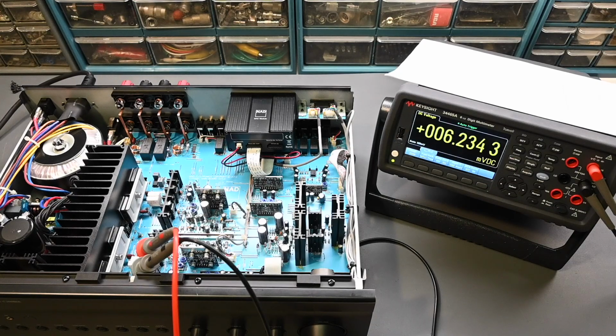You can see it's basically sitting at about 6.2 volts, so it looks perfectly fine. I don't see any issues with that. And keep in mind, 0.2 volts is just 200 millivolts away from the ideal value, so very close. I haven't made any adjustments on this channel. It's exactly the way it was when I connected the test probes, so I'm inclined to leave things just the way they are on this channel.